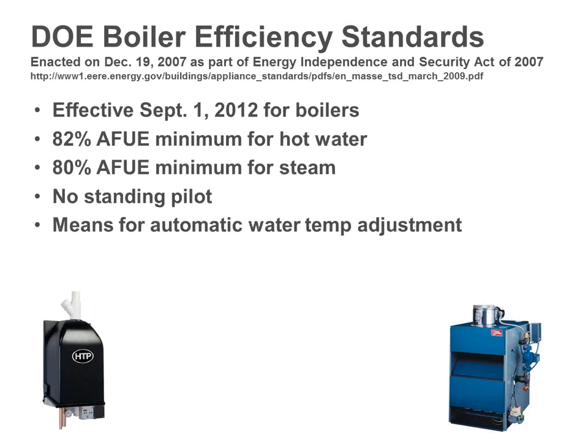I think prior to this, most times boilers were basically bouncing off their high limit. Any zone would call, it would run up to 180 or whatever the limit was set at, and then the next zone would call, and all day long, all year long in heating season, you would be running at 180 degree water. This automatic water temperature adjustment varies from manufacturer to manufacturer, but it's definitely out there, and you're going to have to learn about it. It's not just the old TT connections anymore.